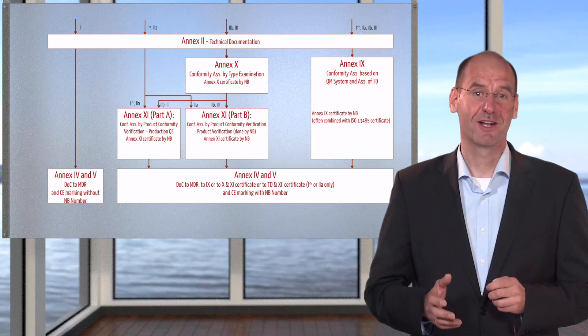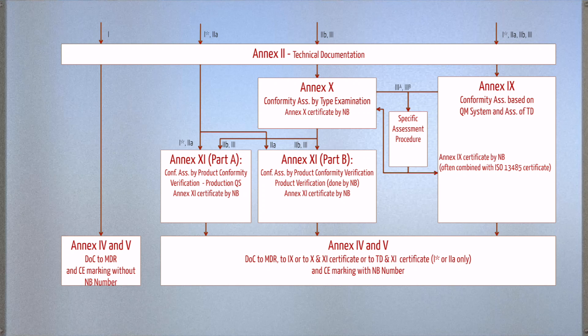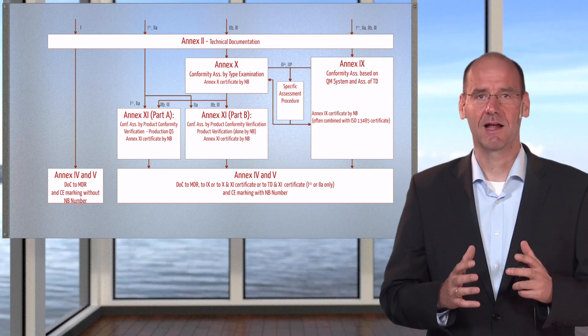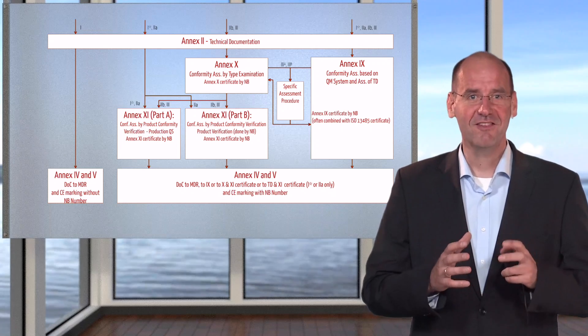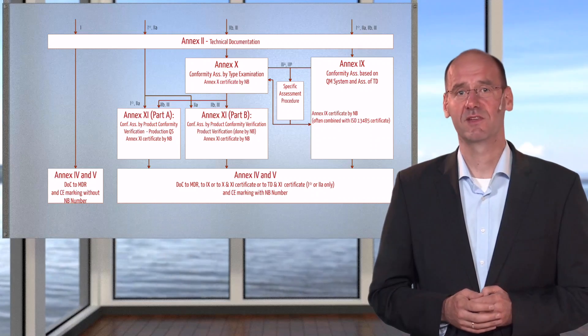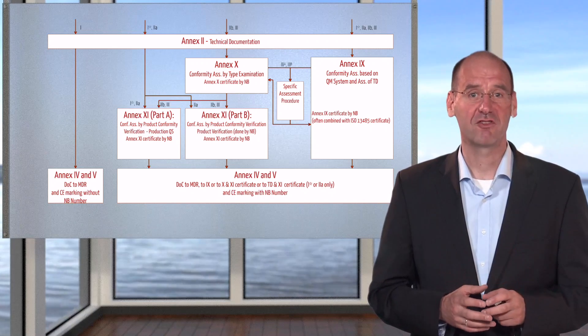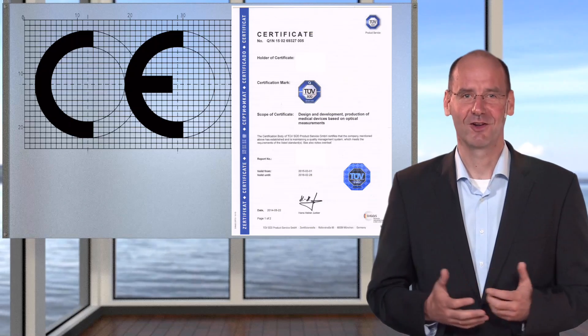For certain highly critical products of class 2B or class 3, there are additional steps required that mandate the involvement of a so-called expert panel, in addition to the notified body. With exception for class 1 products, the notified bodies issue Annex certificates. These are a prerequisite for declaring the conformity and for affixing the CE mark. Therefore, some manufacturers call the procedure the CE certification, even though there is no CE certification.